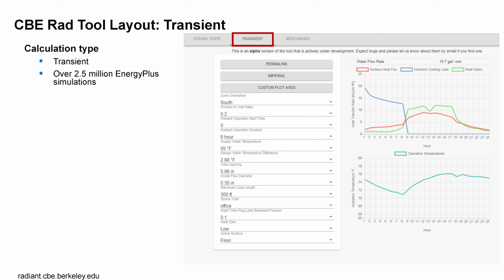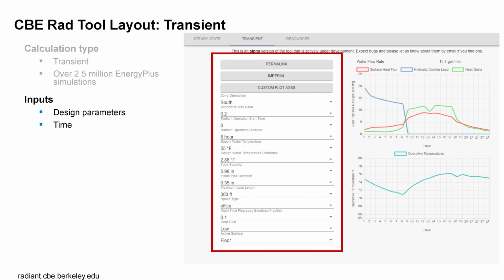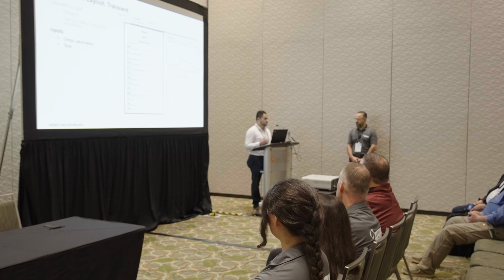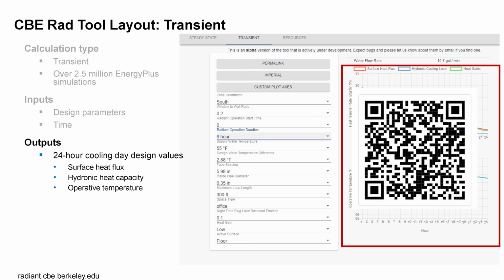So now let's take a look at the transient section of the tool. The transient calculations are based on over 2.5 million EnergyPlus simulations, and the results of these simulations are available to you by selecting a few key input parameters arranged on the left-hand side. One of these important parameters is time. You can select the time your radiant system starts operating and for how long. Time is an important parameter for radiant systems that have their tubing embedded in the concrete and other high mass materials because, as we discussed earlier, with the high response times of these systems, it's really difficult to predict what the effect is going to be from this high thermal mass system. And by including time, we can visualize 24-hour cooling design day profiles, and thus you can use this functionality to see how load shifting strategies impact the space temperatures.